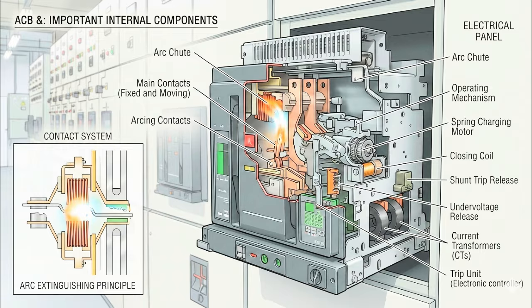The fifth one is the spring charging motor. This motor charges the spring mechanism, which helps in the fast closing operation of the breaker. The next part is the protection relay and sensors. These commonly monitor electrical parameters and provide accurate operation.